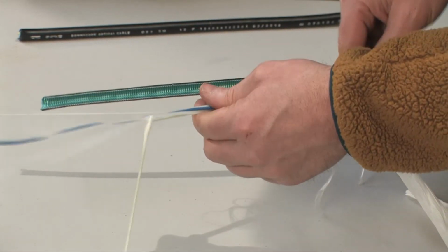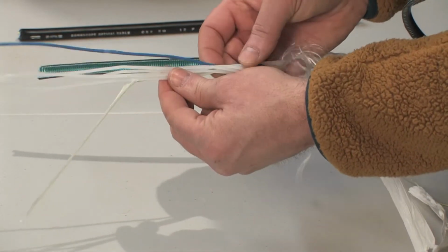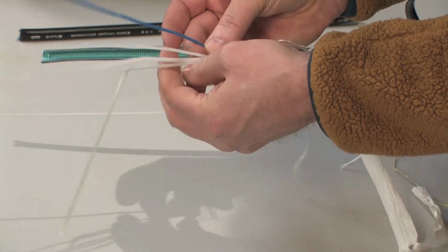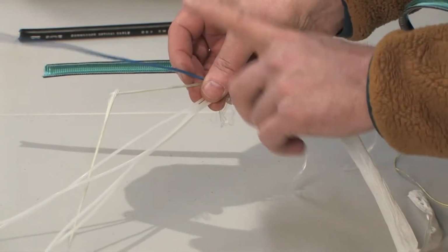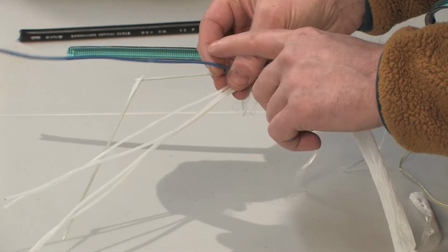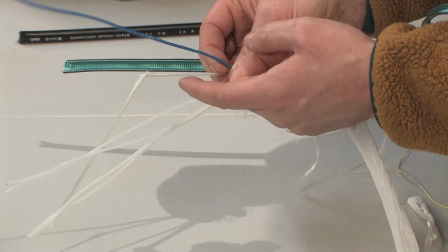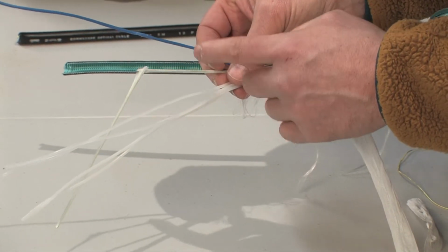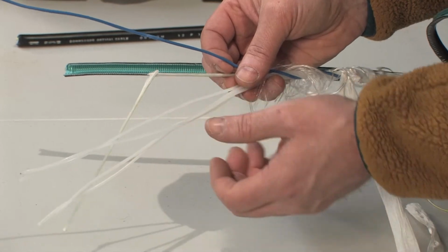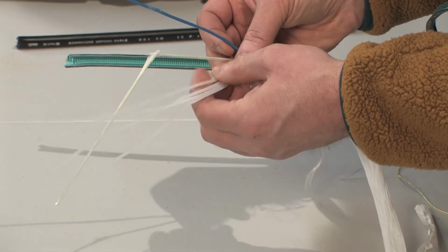Next section that we see here is that we have one blue tube, and then we have several appearing clear or white colored tubes. In this particular case, we have a 12-strand fiber. 12-strand fiber generally means it's going to be one buffer tube. That would be this blue tube. In the color coding of things, blue is usually the first tube, then we would have an orange tube, we'd have a green tube, we'd have a brown tube, slate, white, in order until we run out of colors, which I don't think we can run out of colors at this point.